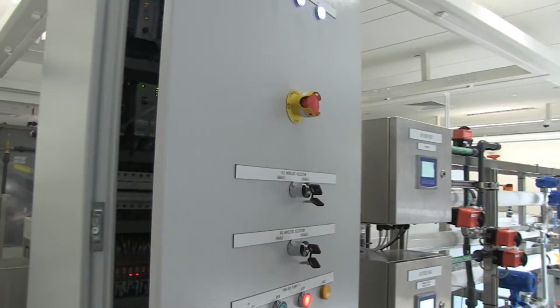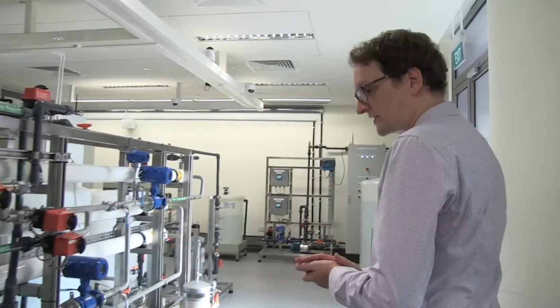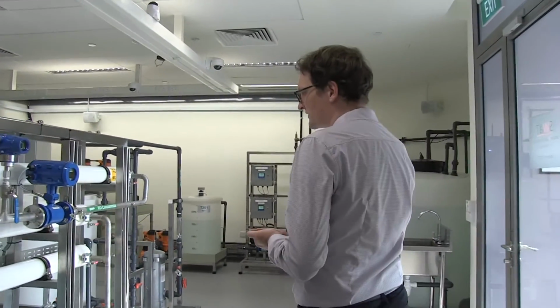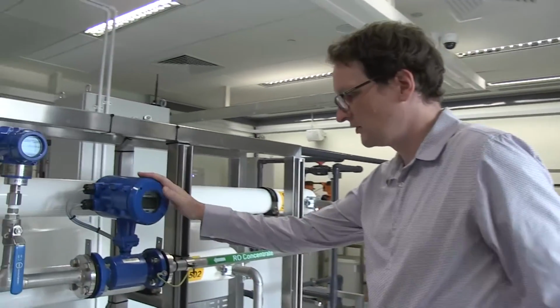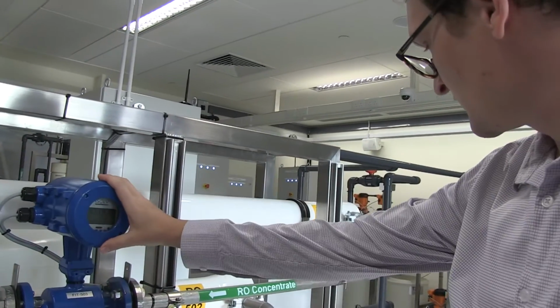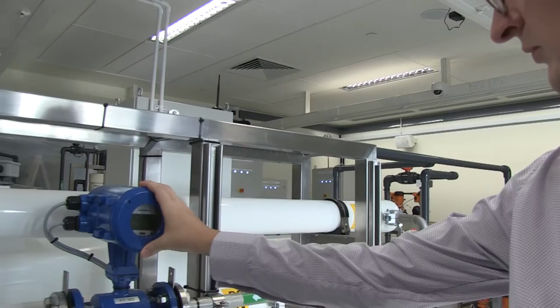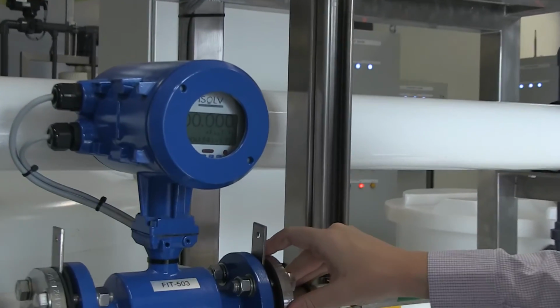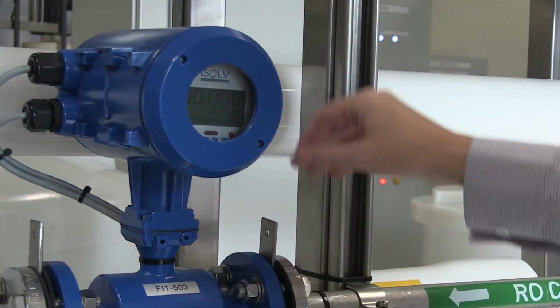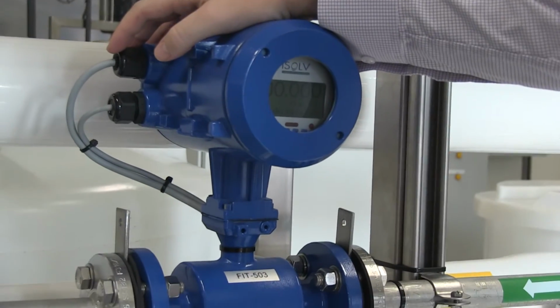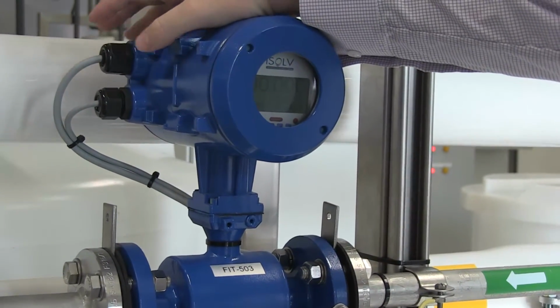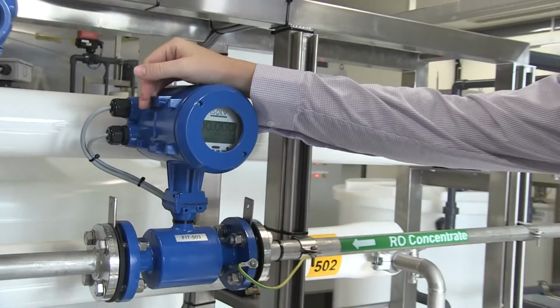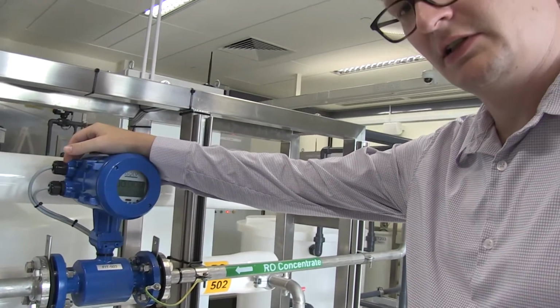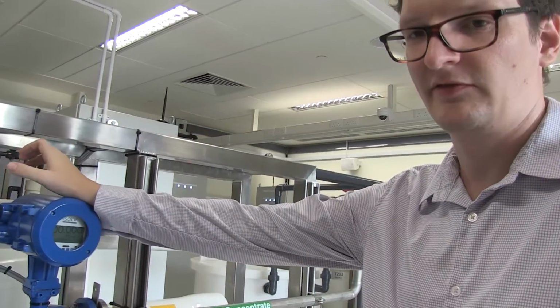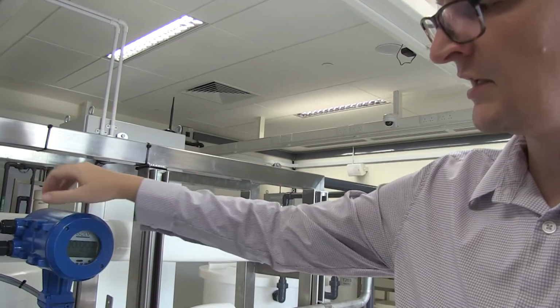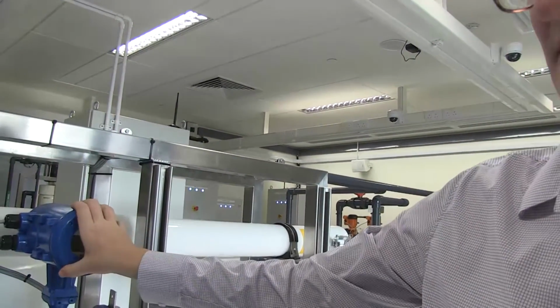Now we can have a look at one example sensor. This is a flow meter, for example. This flow meter is measuring, of course, the flow of water through this pipe. The flow meter itself is an analog component, so you see there are 2 cables coming into the housing here. It receives power, of course, and in addition it provides a current-based analog signal.